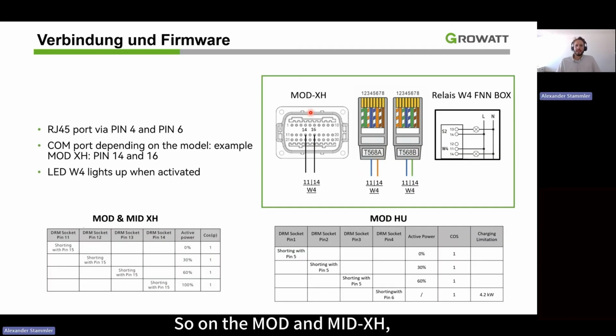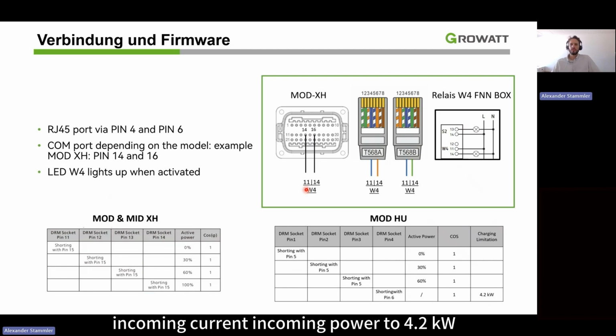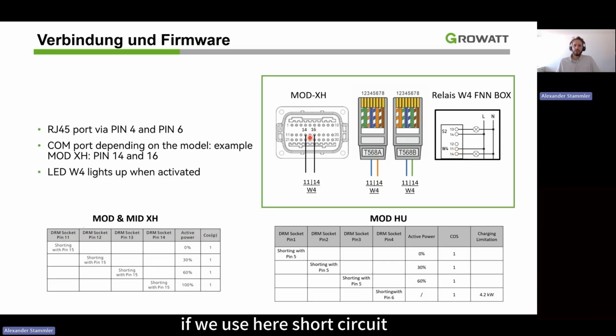Yeah. So on the mod and mid XH, you use pin 14 and 16 for the paragraph 14A. This one shows only the paragraph 14A, so limitation of incoming current, incoming power to 4.2 kilowatt. So if you connect these two to the switch, to the relay, in this example relay 4 with pin 14 and 11, and the grid provider says now, then here we have a short circuit. And if we use short circuit, then the battery will only be able to be charged with 4.2 kilowatt. So charging limitation to 4.2 kilowatt is shorting pin 6 and pin 4.